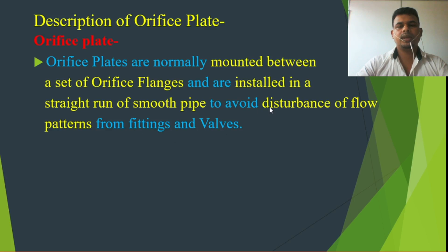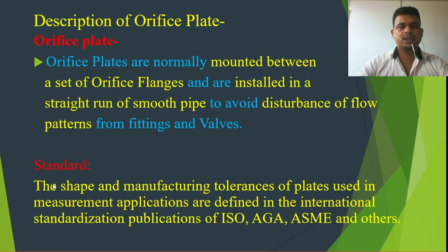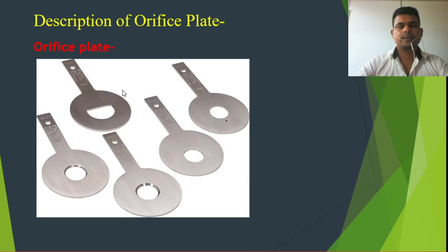We should not install the orifice plate near elbows or valves, as that can cause disturbance of the flow. As a standard, the shape and manufacturing tolerances of plates used in flow measurement applications are defined in international standards such as ISO, AGA, ASME, and others. From the photos you can see different types of orifice plate bore — there is the eccentric bore, the quadrant bore, and the segmental bore.